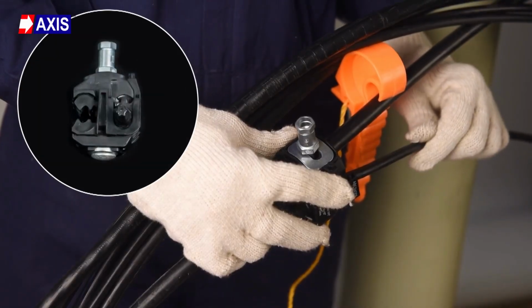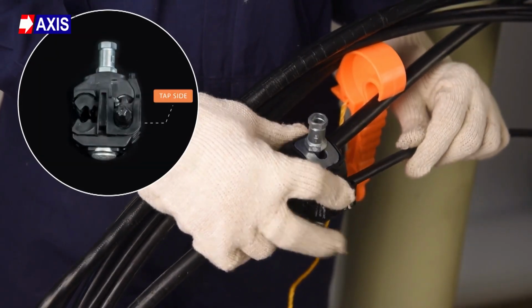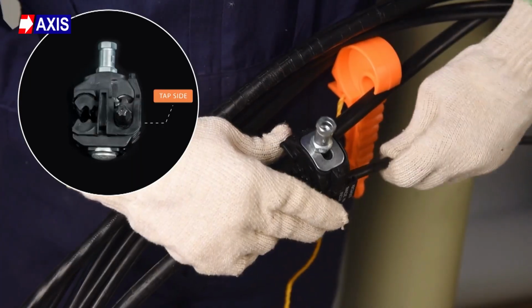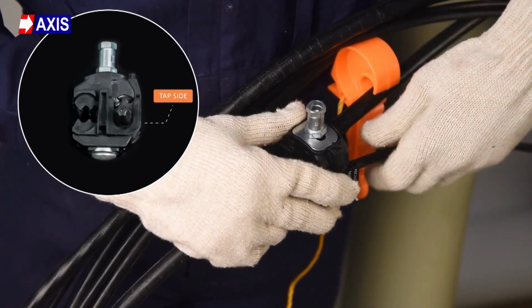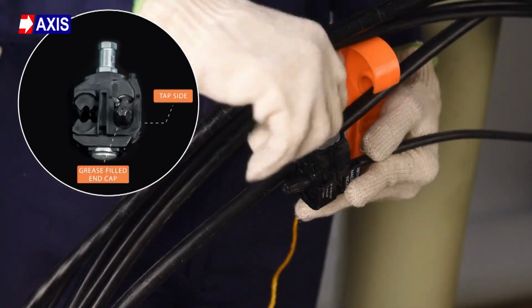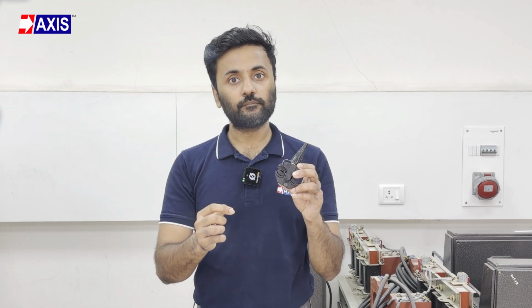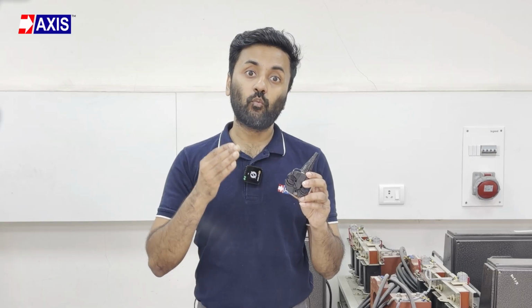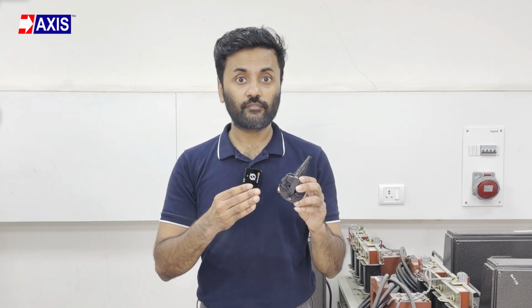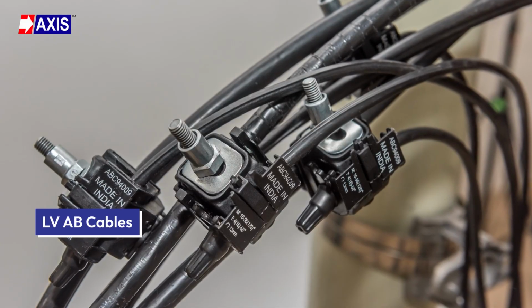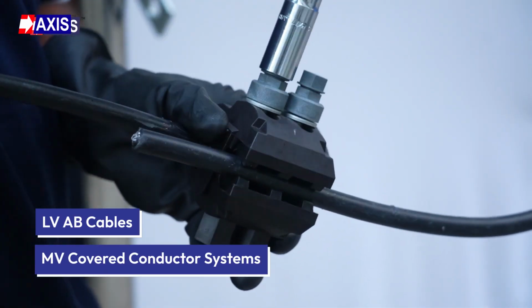Insulation piercing connectors, or IPCs, connect insulated cables without stripping the insulation. When you tighten the bolt, sharp metal teeth inside the connector pierce through the insulation and make contact with the conductor. This creates a secure, low resistance and waterproof electrical connection. At Axis, we manufacture IPCs for two different kinds of distribution systems: IPCs for low voltage aerial bundled cables and medium voltage covered conductor systems as well.